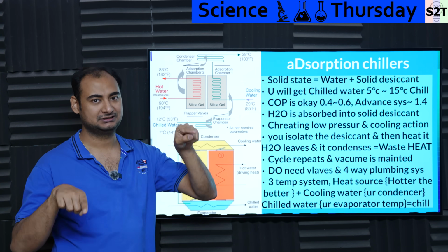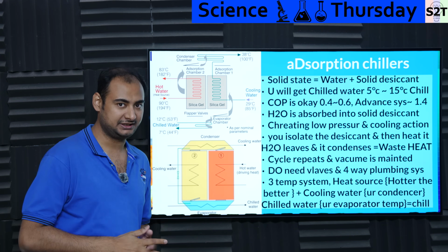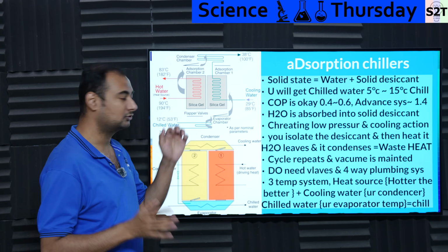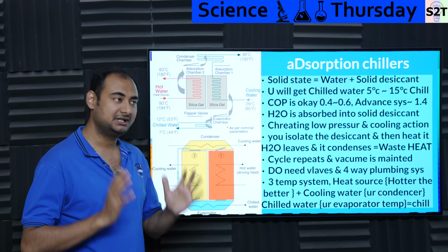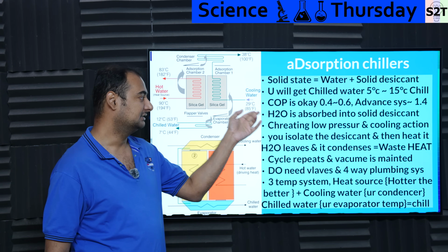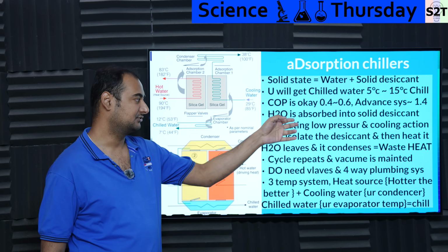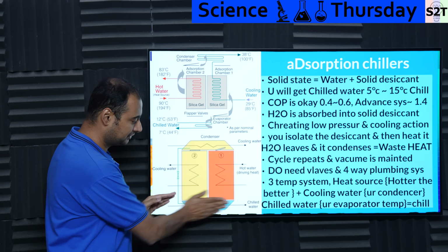That delta has shrunk, or basically what we call low grade heat. This can work in low grade heat. COP won't be great. The cooling will not be great, but it will still cool and it will not consume water. So that is there. The H2O is a refrigerant in a sealed system, it does not leak. H2O is absorbed. So what you have is chilled water.